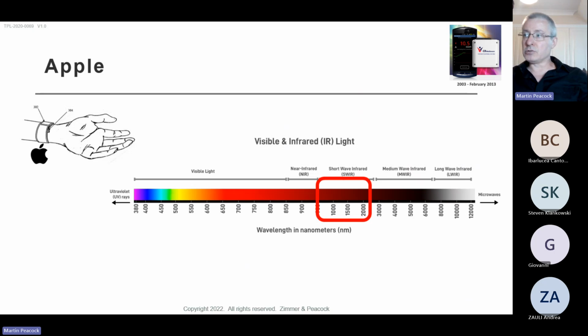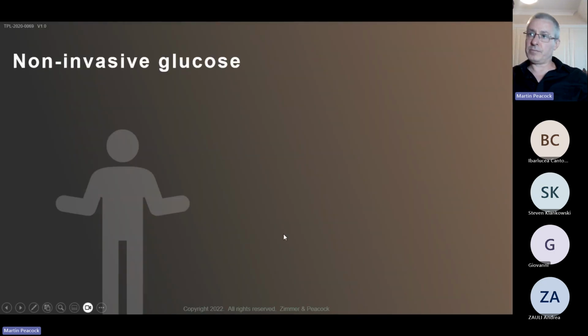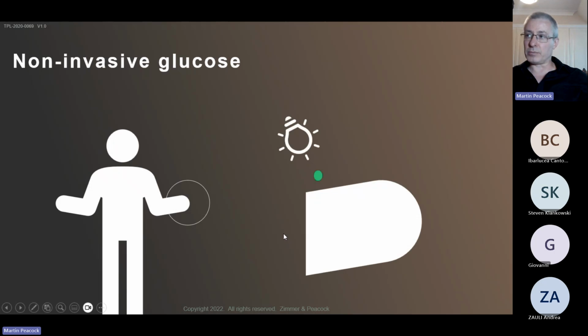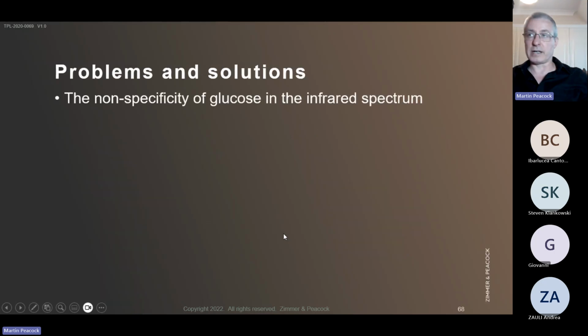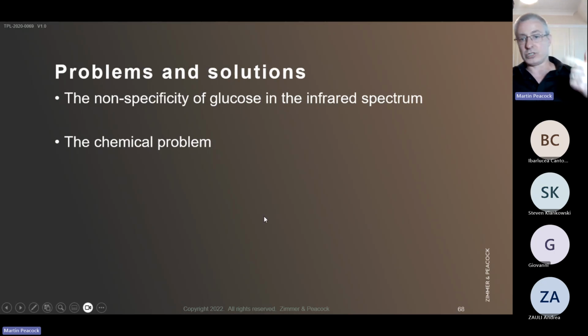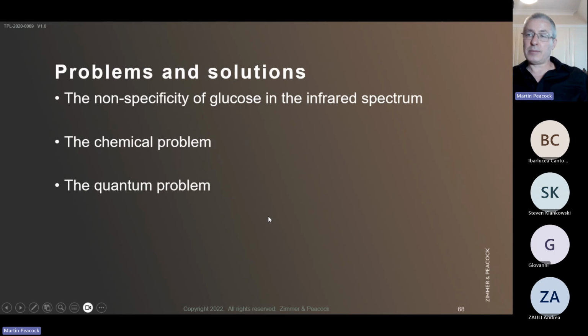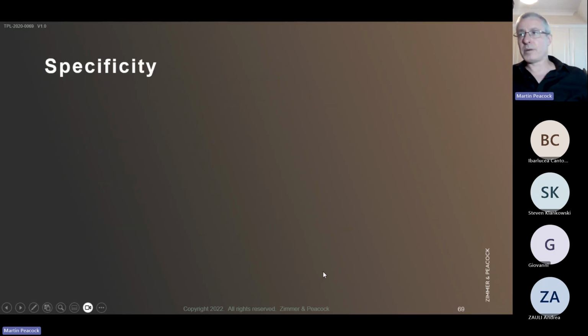So Apple seemed to be using the shortwave and the medium wave infrared. They're obviously trying to put photons in. Those photons are then expected to interact with the glucose, and they get a signal back, and that's what they then have to deconvolute. It's quite hard to measure glucose by infrared spectroscopy. There's a bit of a chemical imbalance between glucose and water, which I will touch upon. Glucose is at 5 millimolar concentration, water is at 55 molar concentration. They might also have a slight quantum problem as well, in that water is also quite good at interacting with photons and is in quite high concentration. So that might give them a bit of a problem, in that the water is causing them a lot of interference. But I will touch upon that.